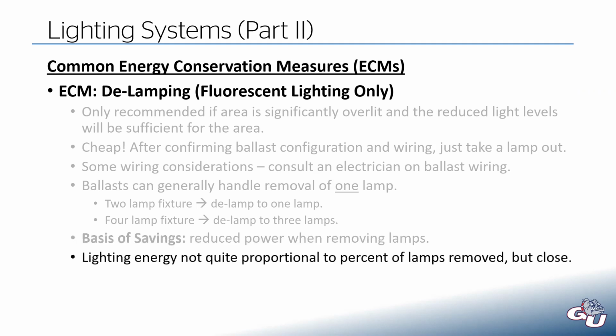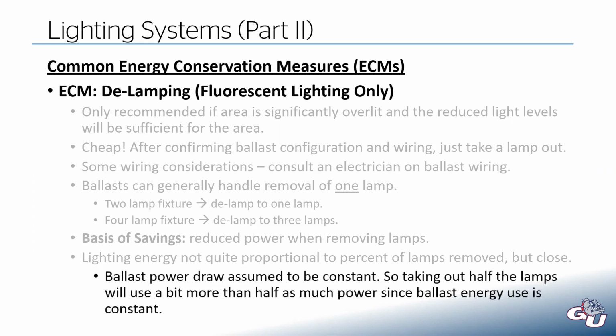And the power and resultant energy you're going to save is not quite proportional to the percentage of the lamps you took out. So if you have a 2-lamp fixture and you take out 1 lamp, on paper you might think, well, I should be saving 50% of my power there, but that's not necessarily the case, and it's because of that gosh darn ballast. So you still have that ballast power draw that the overall fixture needs to make this thing work. And if you take out one of those lamps, you're not really impacting the ballast power draw. So if you take out half the lamps, you're going to use a bit more than half of the power.